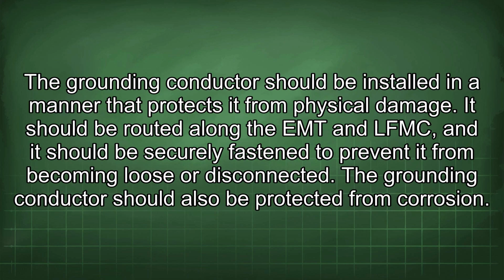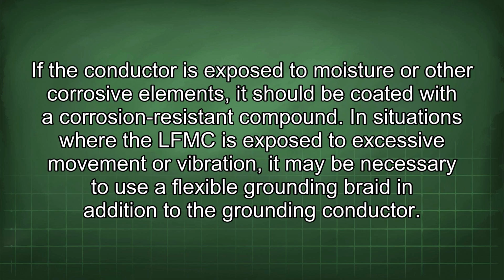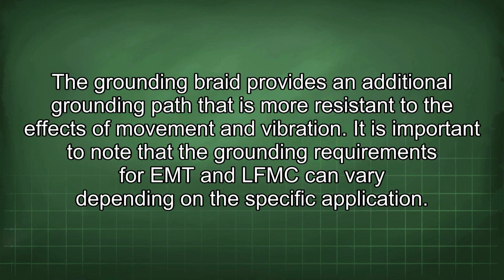The grounding conductor should be installed in a manner that protects it from physical damage. It should be routed along the EMT and LFMC, and it should be securely fastened to prevent it from becoming loose or disconnected. The grounding conductor should also be protected from corrosion. If the conductor is exposed to moisture or other corrosive elements, it should be coated with a corrosion-resistant compound. In situations where the LFMC is exposed to excessive movement or vibration, it may be necessary to use a flexible grounding braid in addition to the grounding conductor. The grounding braid provides an additional grounding path that is more resistant to the effects of movement and vibration.